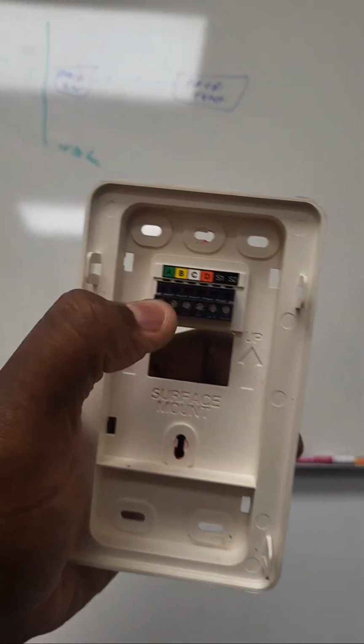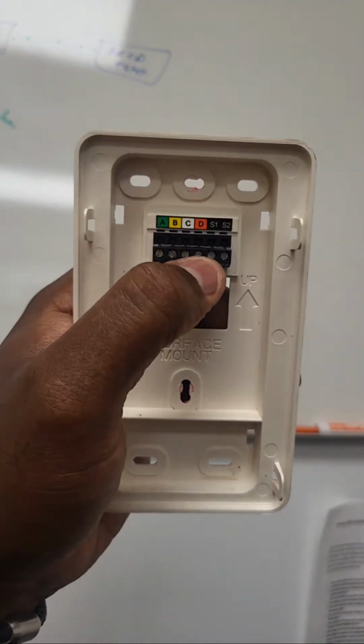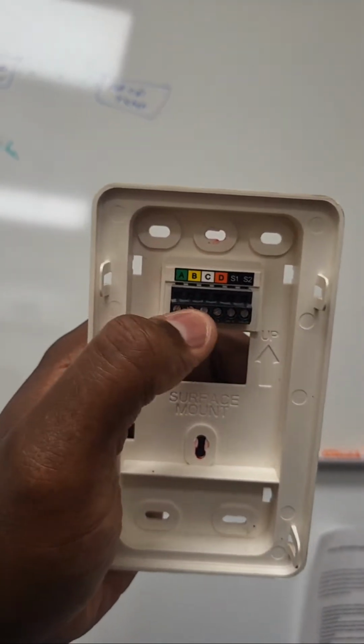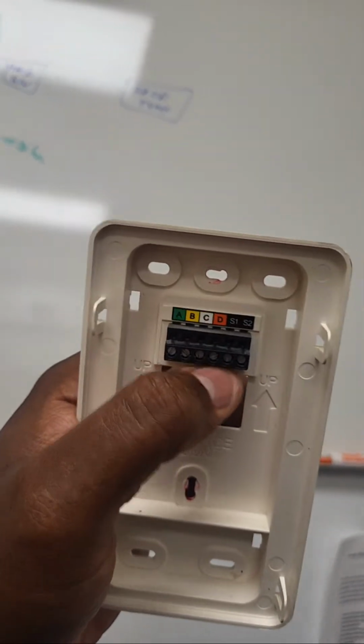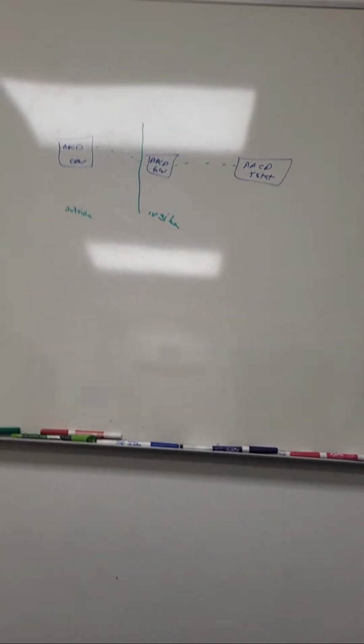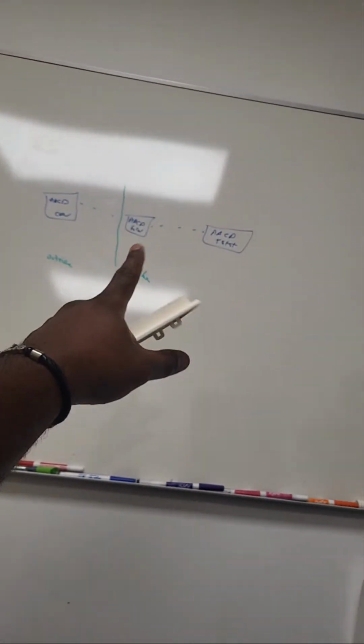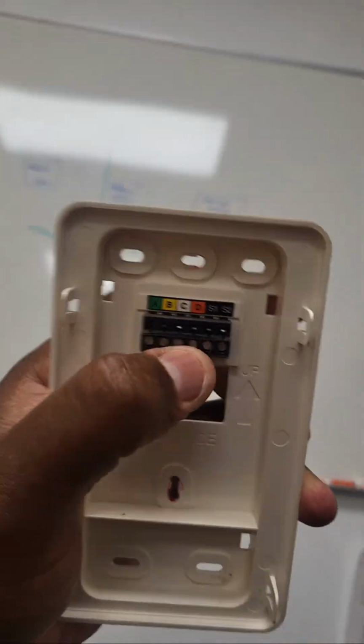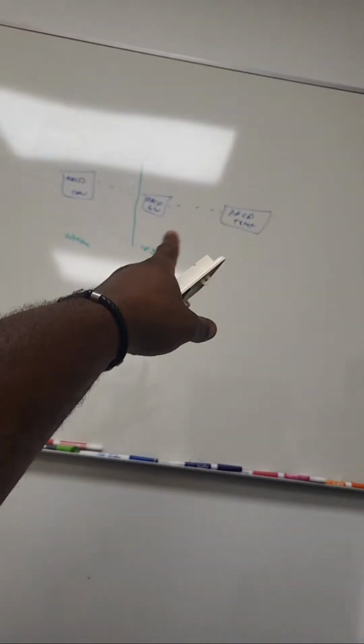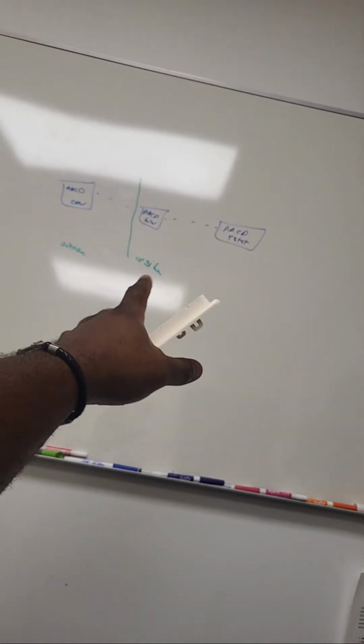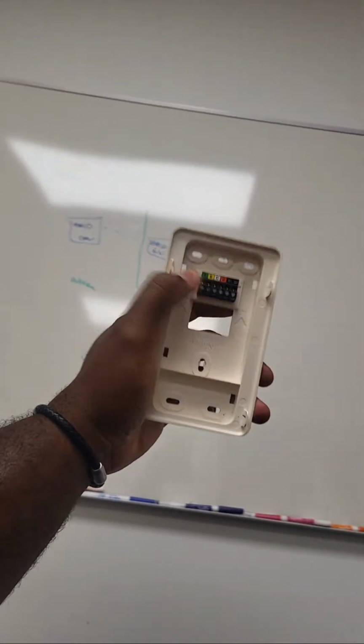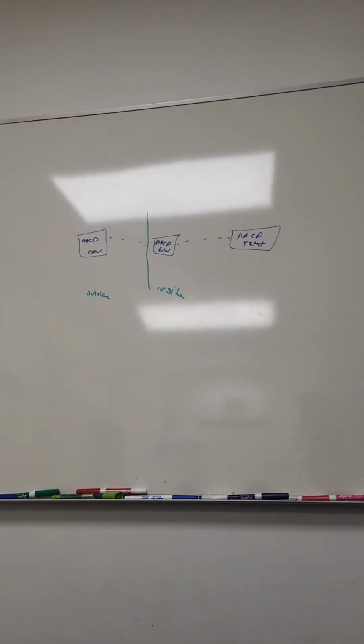The A and B on these communicating thermostats are for communicating, but the C and D is for the 24 volts. So if you hook your meter up between C and D, and you don't have 24 volts, then that means you have to go back to the furnace and make sure you have power. You have to go through your whole shebang, make sure your transformer is working. Make sure that you have 24 volts at the furnace first, because if you don't have 24 there, that does not mean that the thermostat is bad. That means simply that you lost power somewhere at the furnace, and you have to diagnose that issue. And then once you correct that issue and you do have 24 volts leaving the transformer, that's when you can proceed and figure out your way back to this thermostat here.